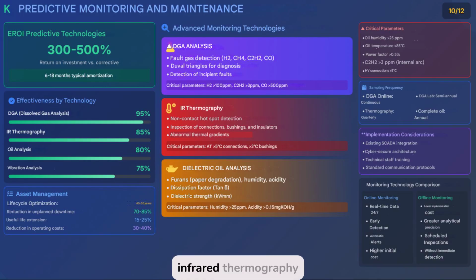Furthermore, infrared thermography allows hot spots in connections, bushings, or insulators to be visualized without the need for physical contact. When the temperature difference across a connection exceeds 5 degrees, this indicates an imminent risk condition that can be anticipated and corrected before it leads to a serious failure. This type of visual analysis can also be used to assess the quality of previous interventions, detect installation problems, and validate the thermal stability of key components.